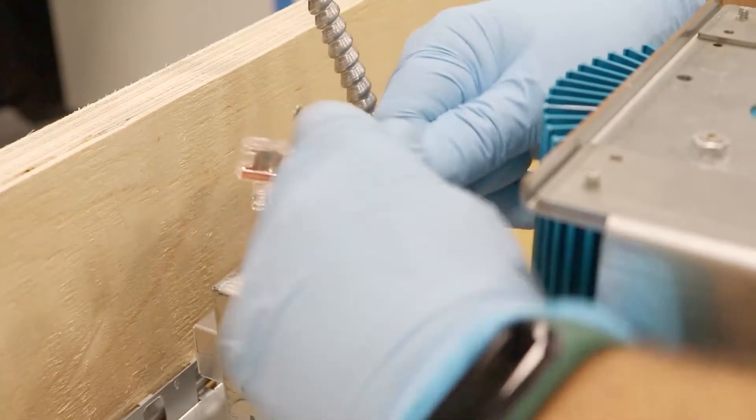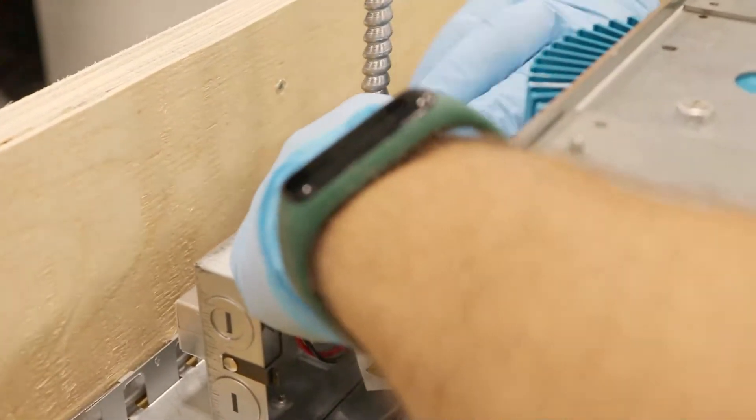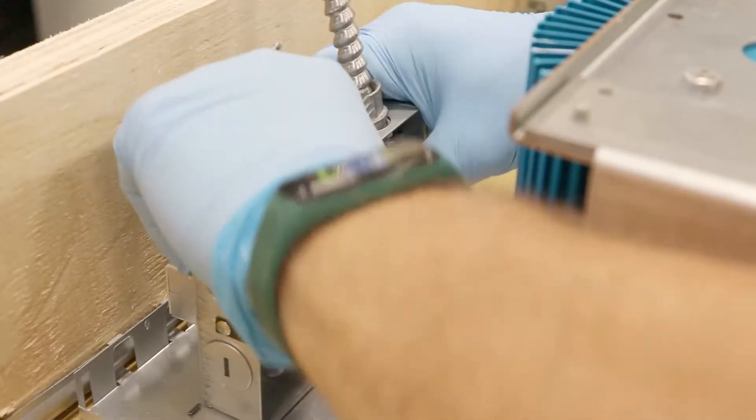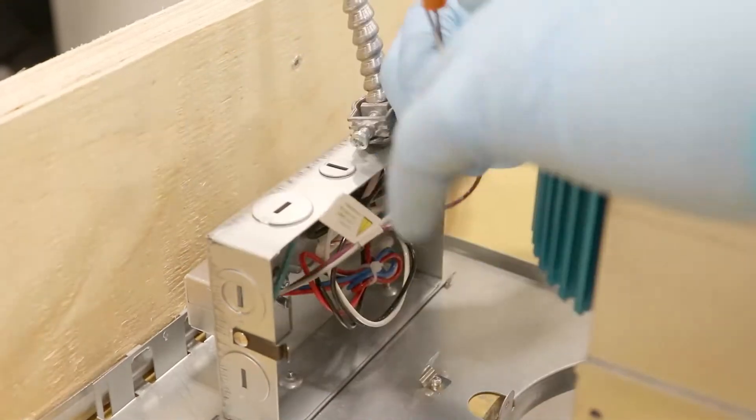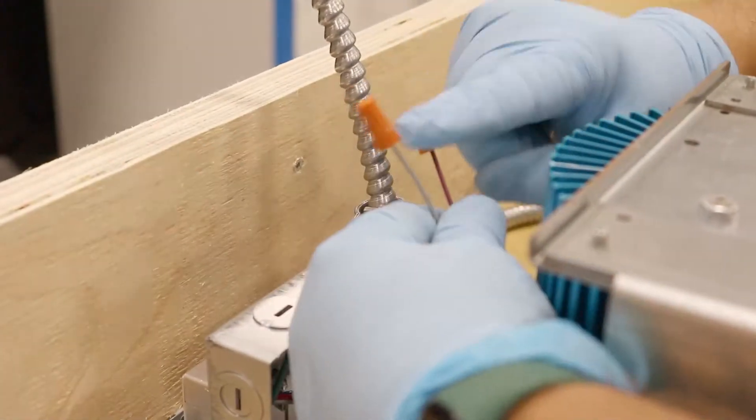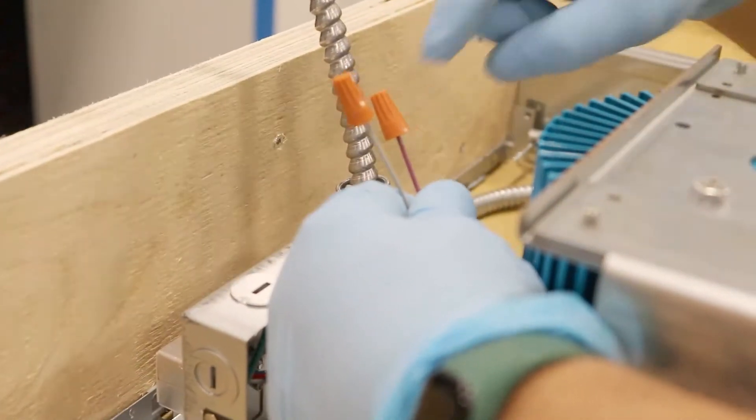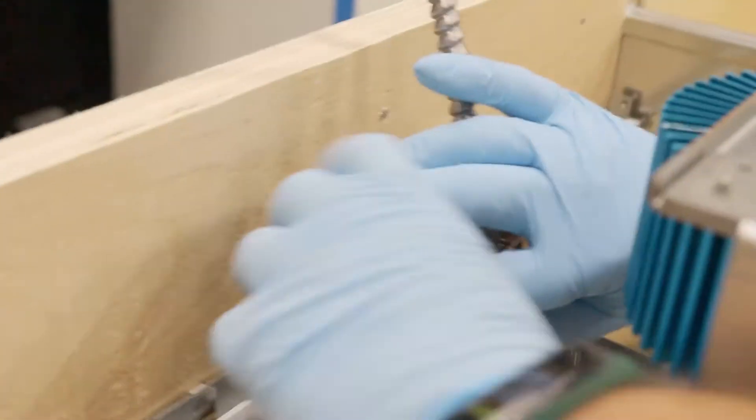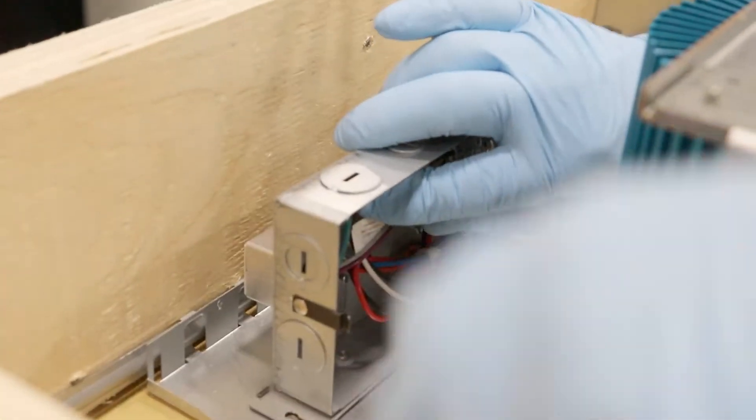If you're using 0-10 volt dimming, connect matching purple and grey wires with twist wire connectors. Apply suitable wiring diagram for fixture. Make certain there are no exposed strands of wire. Place all wiring and connectors back in junction box and return the cover.